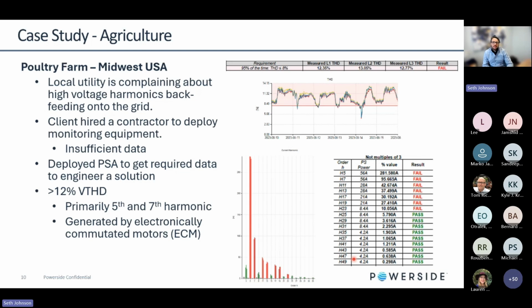So the utility was kind of pushing this and pushed the client to hire a contractor to deploy some monitoring equipment. Eventually that data got sent over to us because they wanted to look at providing a solution for the harmonics, but the data was insufficient. For example, they used a meter that was only able to look at total harmonic distortion. It wasn't able to look at individual harmonics, which was something that was needed for this application.